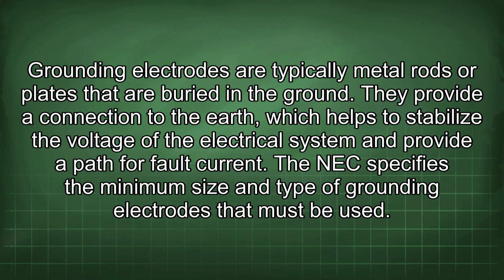Grounding electrodes are typically metal rods or plates that are buried in the ground. They provide a connection to the earth, which helps to stabilize the voltage of the electrical system and provide a path for fault current. The NEC specifies the minimum size and type of grounding electrodes that must be used.